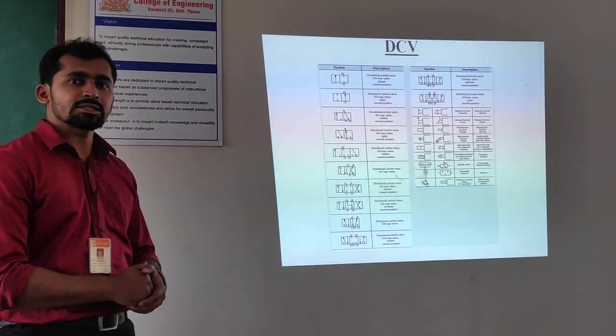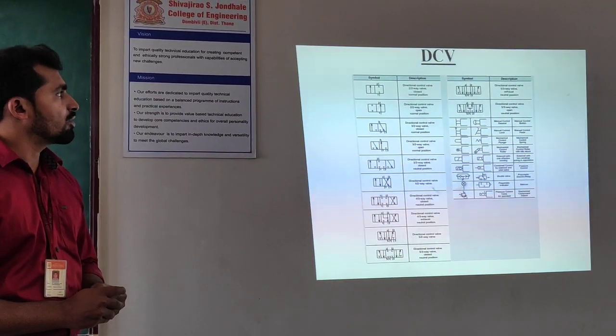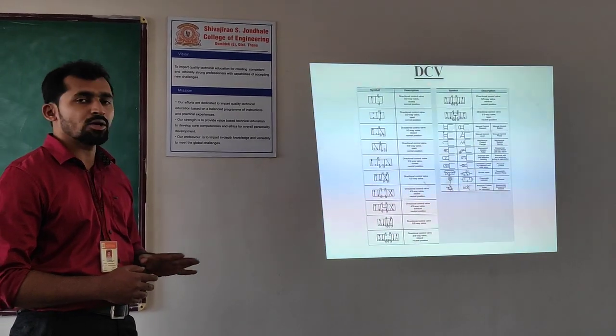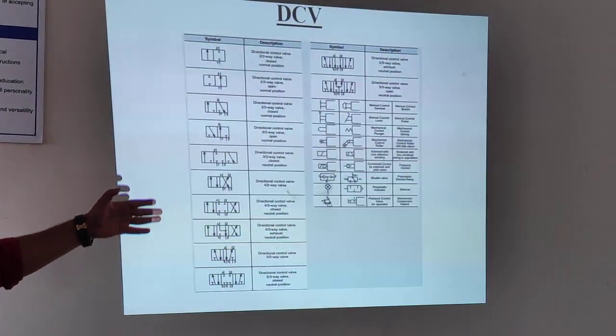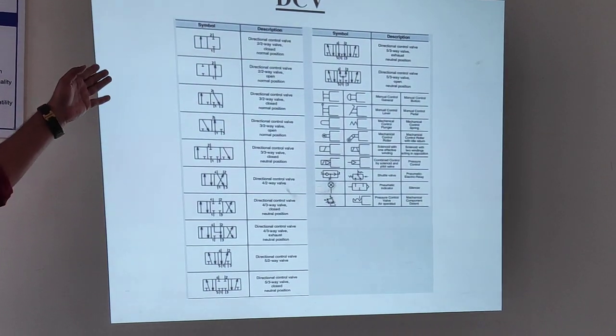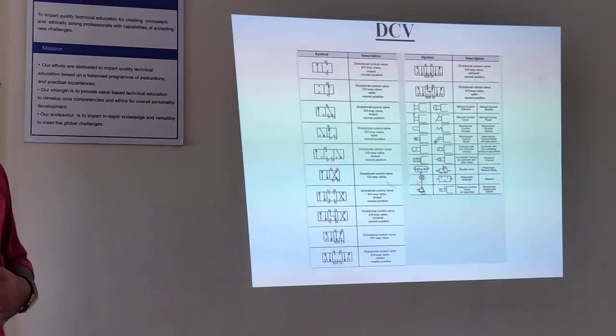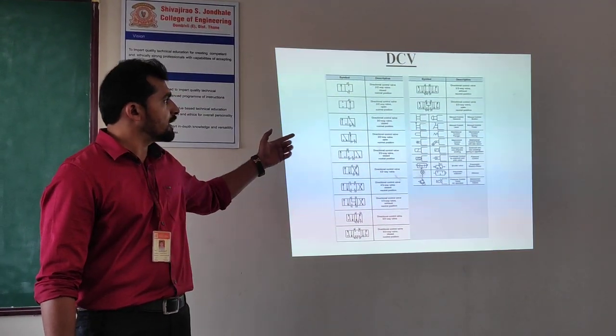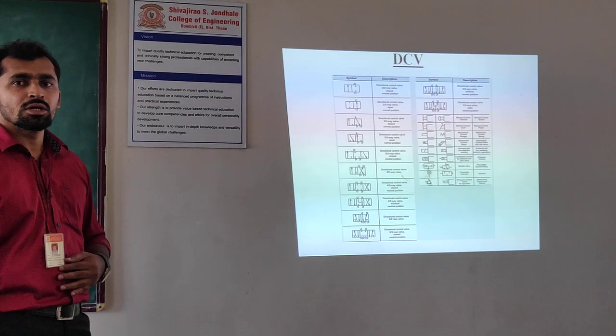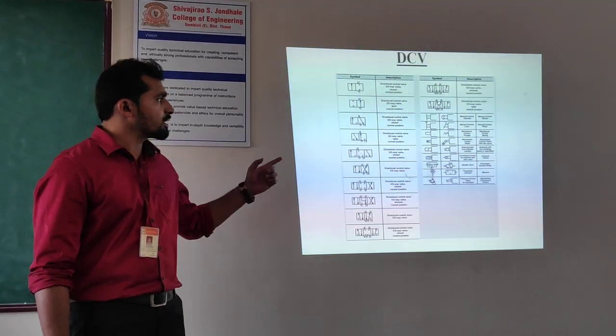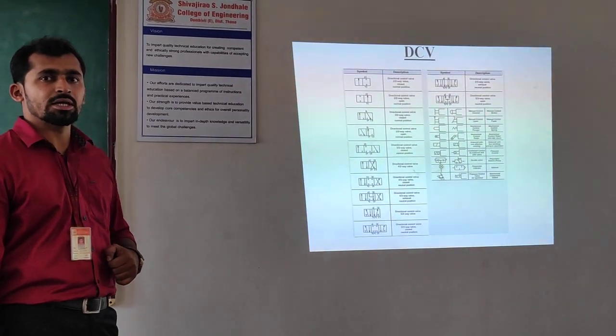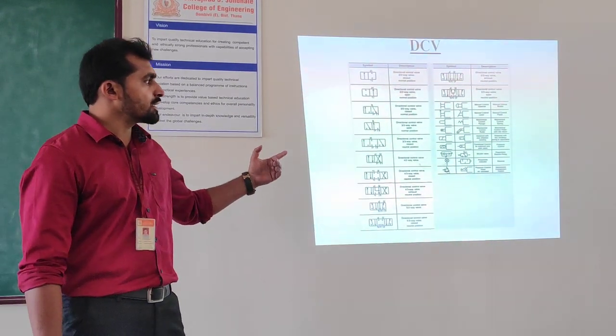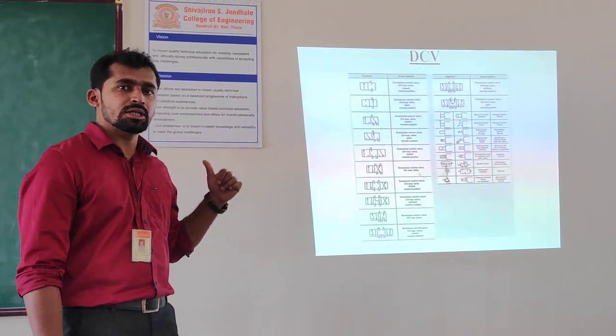Next is DCV — that is, directional control valve. A directional control valve is used to pass the fluid or compressed air in a particular direction. There are a number of directional control valves: 2x2, 3x2, 4x2, 5x2, 5x3, etc. Generally, for a single acting cylinder the 3x2 directional control valve is used, and for double acting cylinder the 5x2 directional control valve is used. We will discuss the directional control valve in detail when we see the electro-pneumatic circuit.